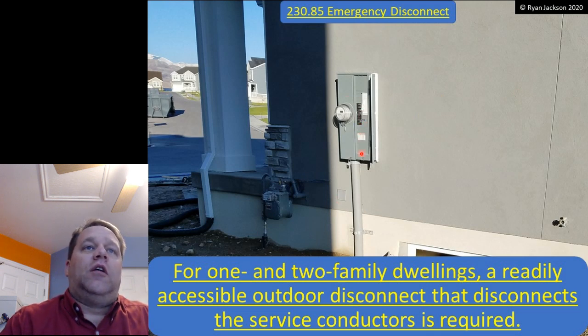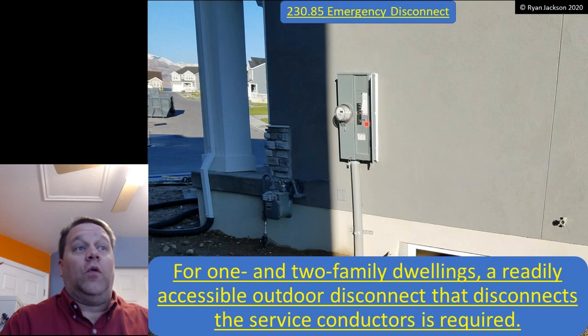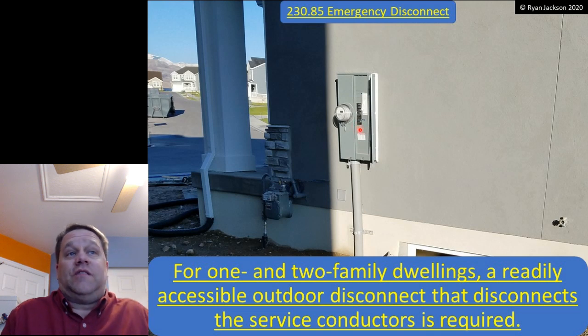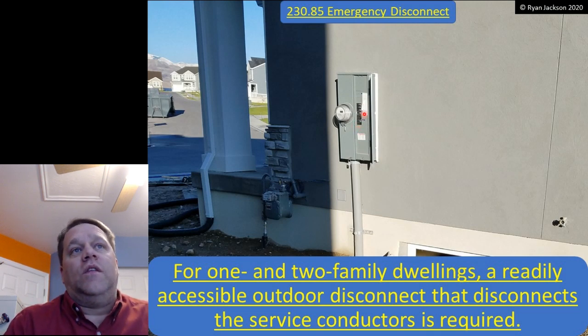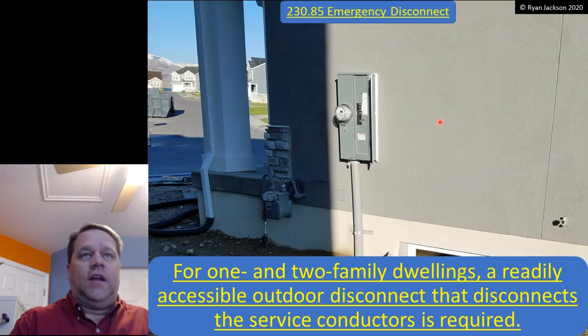Now, this panel board, as you can see, is a combination unit. It has the meter, and then in there it has a service disconnect. Only one service disconnect, right? Not two to six in the same enclosure. We know that's not allowed anymore. So one service disconnect, walk up, shut it down.